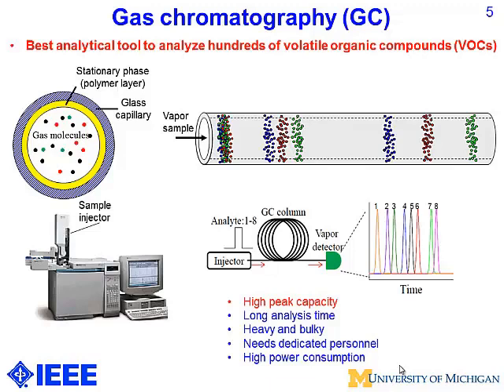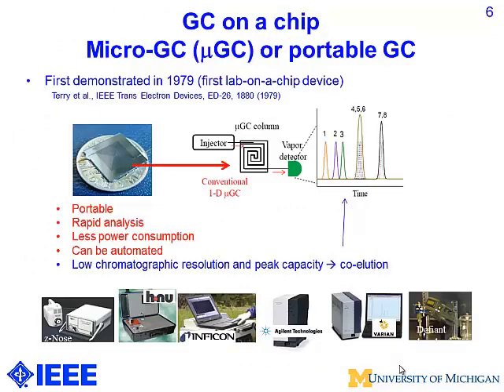The principle of GC is that you inject analytes in a pulse format, they travel along the column, and they get separated — so eight analytes in gives eight peaks out, each representing one analyte. The advantage of a large GC is a very large peak capacity, meaning you can separate hundreds of analytes. However, it takes extremely long time — usually hours — it's very heavy and bulky, needs dedicated personnel, is in a centralized lab, and consumes lots of power. For field applications, we need a micro-GC.